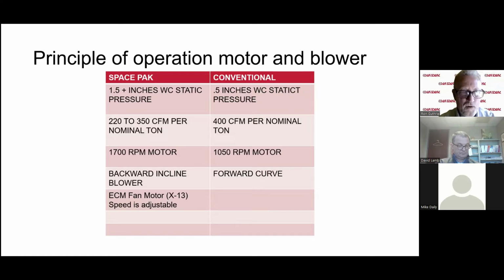We want to shoot for the sweet spot. Okay, so just write that down in your notes. 250 CFM per ton is really what you're looking for. Sometimes we can go a little bit higher than that in some instances, which would typically be a retrofit application. If we can get 220, then we're going to be okay. We're just going to have a noisier system and more marginal than at 250 CFM per ton.